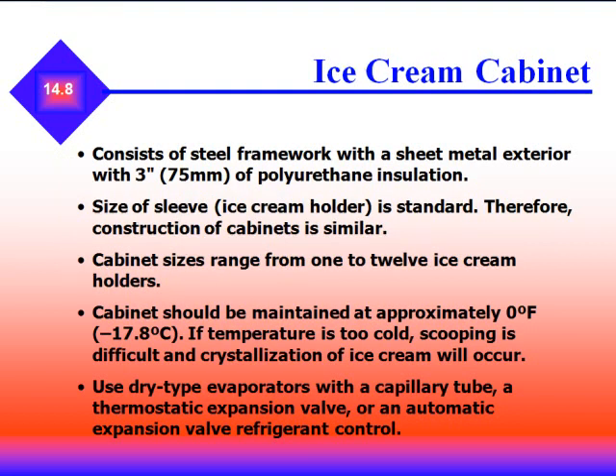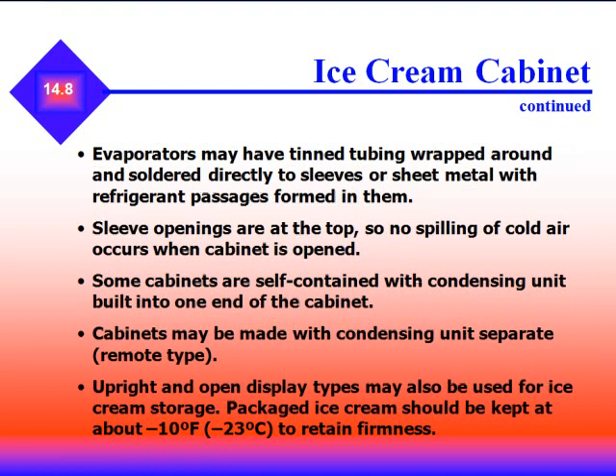Ice cream cabinets, as found in convenience stores, consist of a steel framework with sheet metal exterior and 3 inches of polyurethane insulation. Cabinets range from one to twelve ice cream holders and should be maintained at approximately zero degrees. If the temperature is too cold, scooping is difficult and crystallization of ice will occur. They use a dry type evaporator with capillary tube, thermostatic expansion valve, or automatic expansion valve. Sleeve openings are on top so no spilling of cold air occurs when the cabinet is opened. Some cabinets are self-contained; others use remote condensing units. Packaged ice cream should be kept at about negative 10°F to retain firmness.